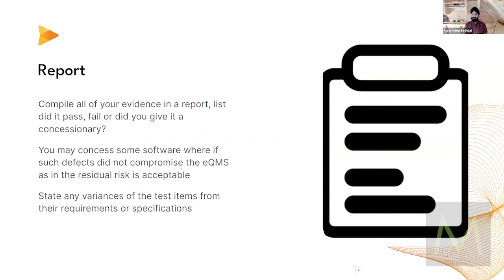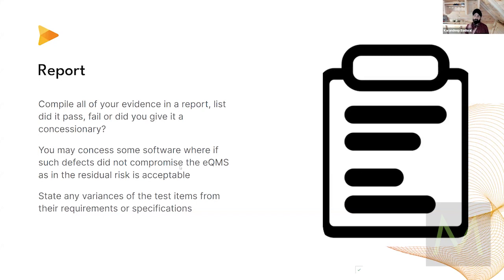How do you actually do it? Some companies simply make the mistake of writing a validation report saying we're going to do X, Y, Z, we did it, tick a box and sign it. But where's your evidence? The most rational way is to take screenshots of what you're doing — if you're looking at user access groups, take a screenshot of your whole page with the time and date at the bottom, which shows you actually did it on that particular date. Videos are another option. Don't just sign a report saying you did it — that doesn't mean anything. If you have a screenshot of evidence, that's valid. And outside of requirements and regulations, it's just common sense to validate your systems.